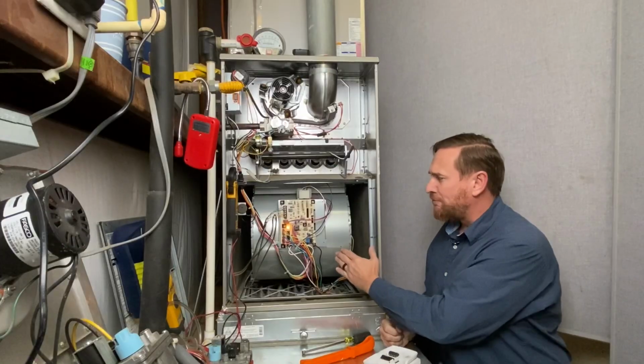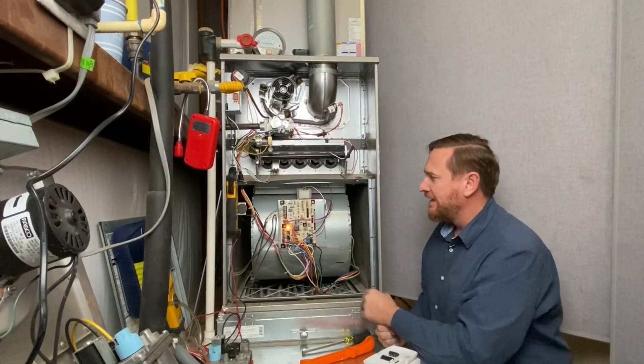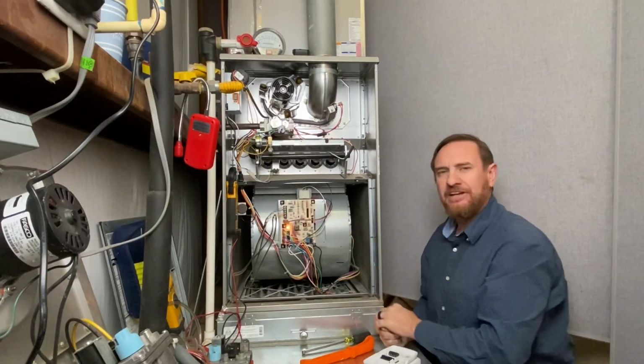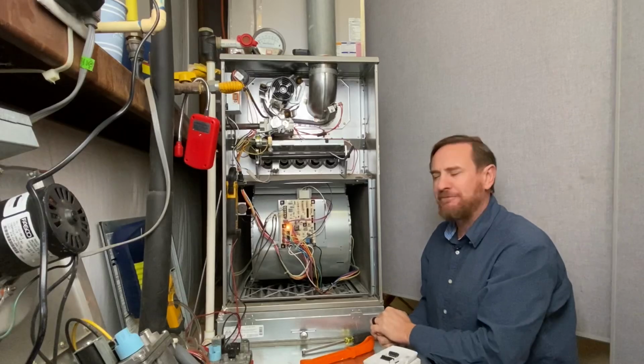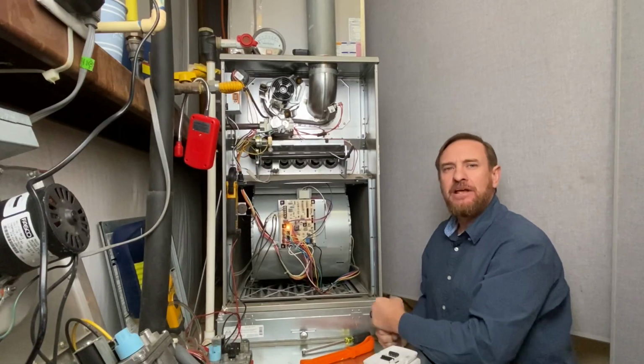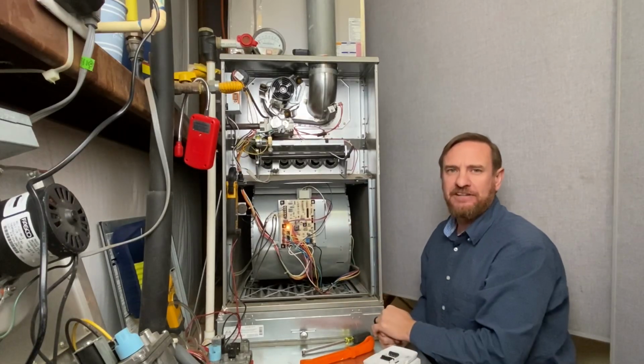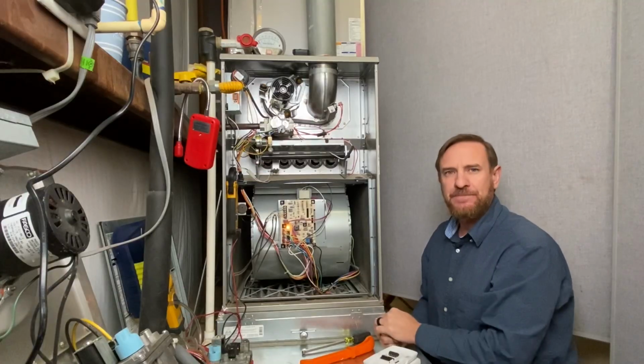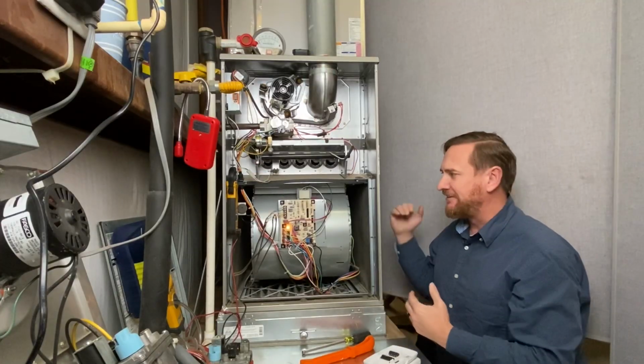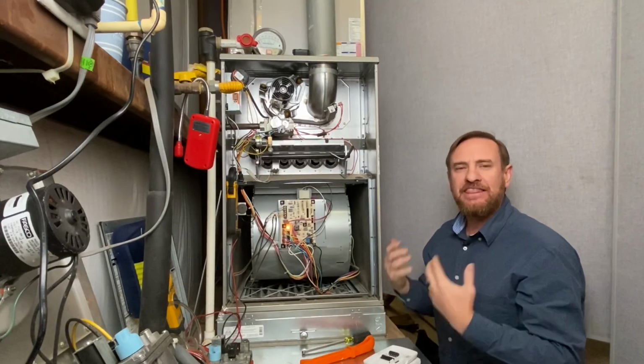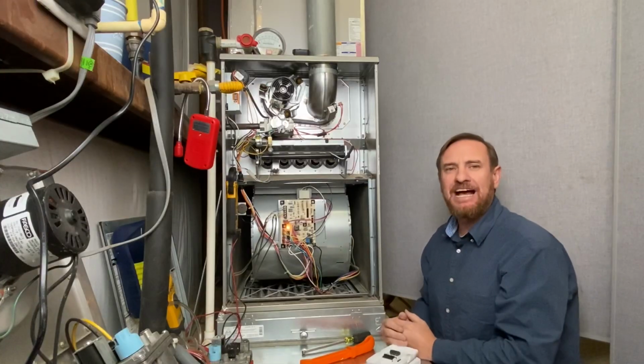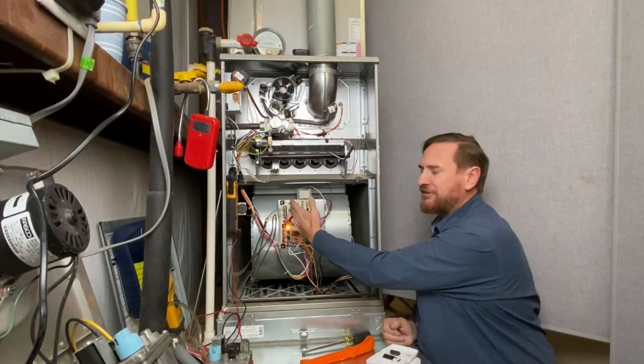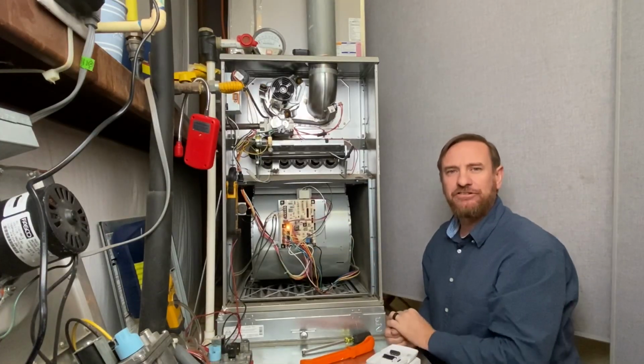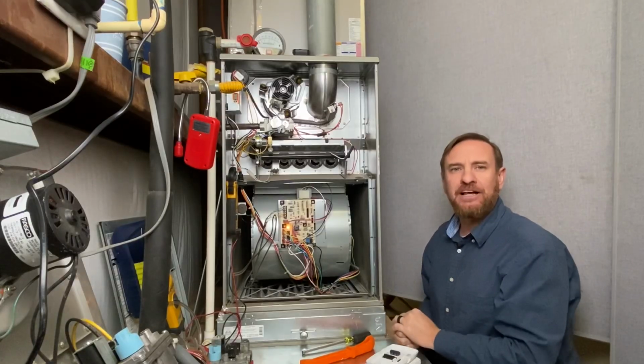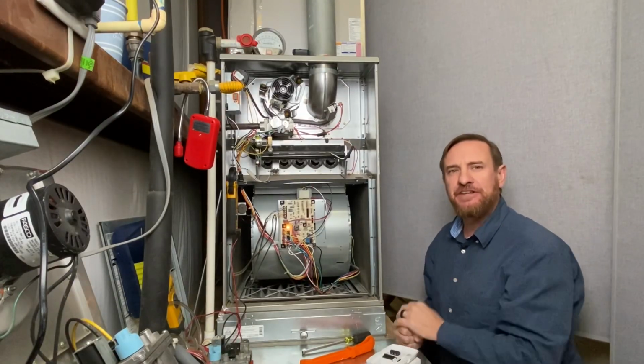Some of these control boards have an adjustable off delay. This particular one does. It has actual jump terminals. Some of them have dip switches that we use, but you can adjust how long that off delay happens. For example, you have an elderly customer, as this thing is cooling off the heat exchanger, they feel what they call a cool draft in the house. They don't like that. You can actually slow the blower delay down to where it only runs for a shorter period of time. So that way they don't feel that cool draft.